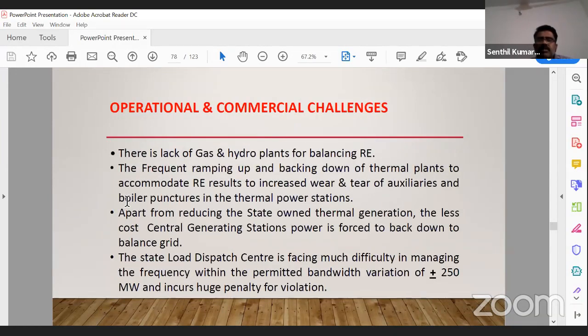What are the operational and commercial challenges faced? Gas and hydro stations balancing the RE power. The frequent ramping up and backing down of thermal plants to accommodate RE results in increased wear and tear of auxiliaries and boiler punctures of the thermal power station.